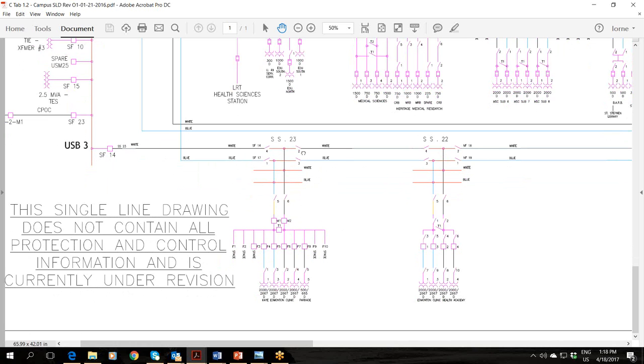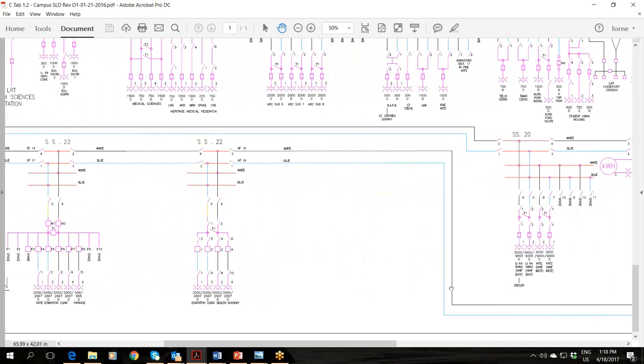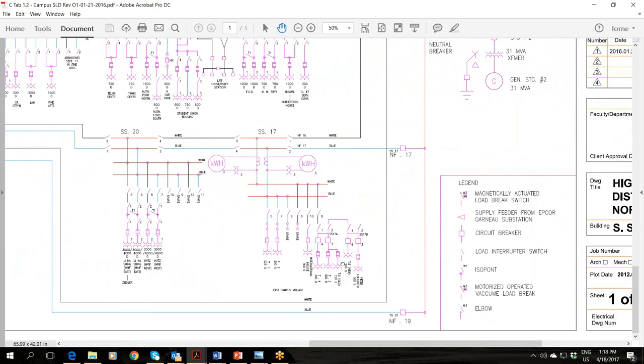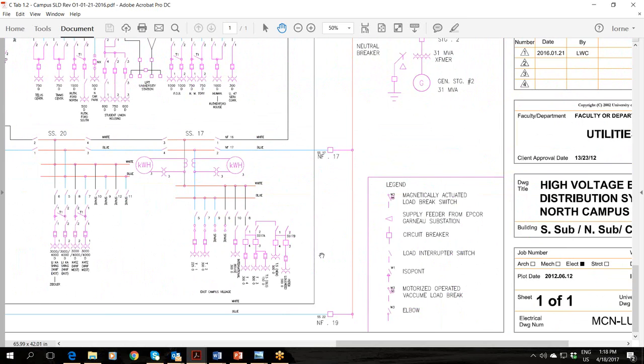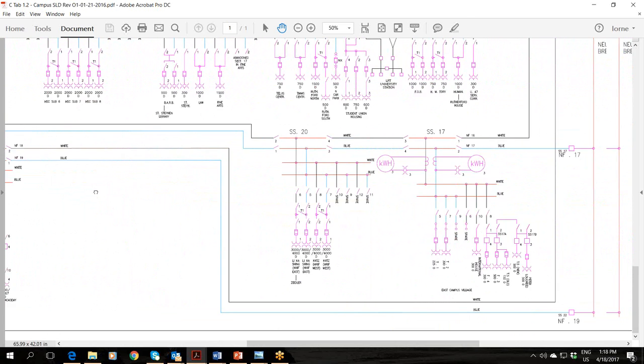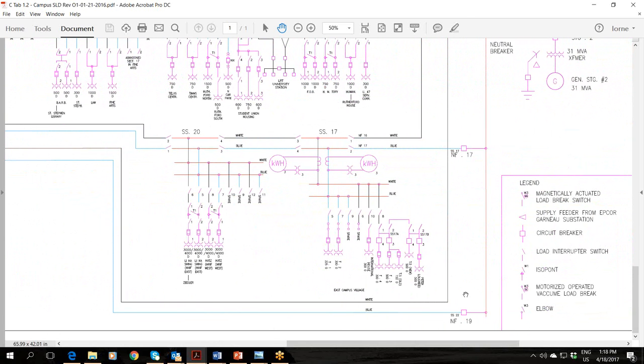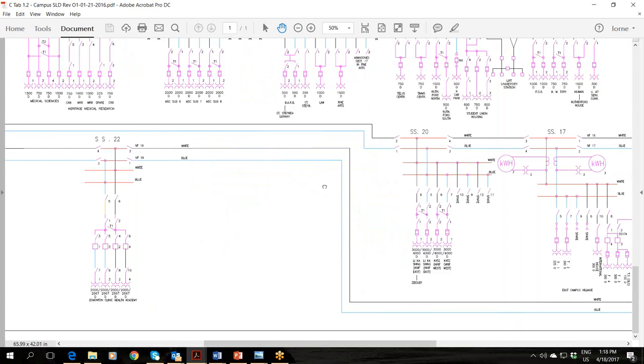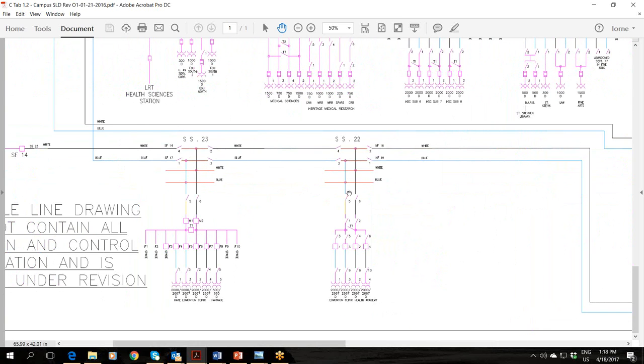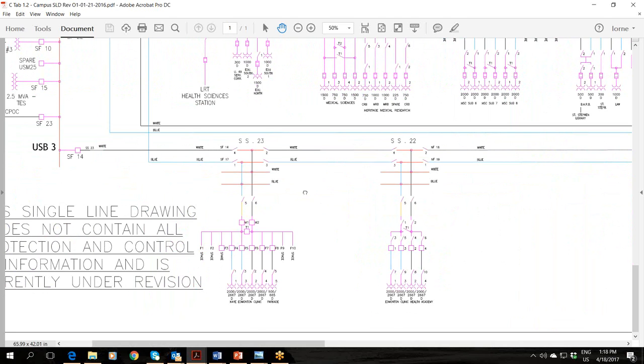But in terms of the flow through from the south switching station over to the north switching station, again, you got this blue-white through a set of switches, through another set of switches, finally ends up its way over at the north switching station. We do not operate generally with all of these switches and breakers closed. Typically, we'll say have this breaker open. So our architecture, we call it a complex radial. So it is a radial supply ultimately, but as you can imagine, it's got lots of different configuration options, which gives us a lot of flexibility in operating the system.